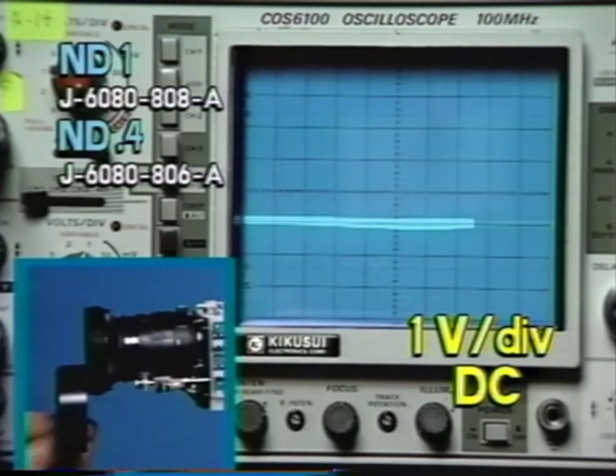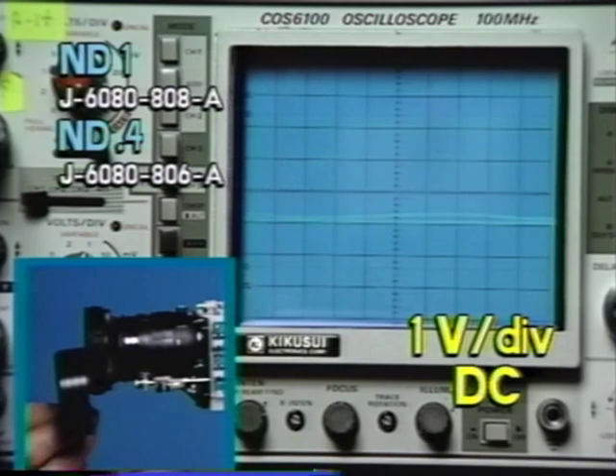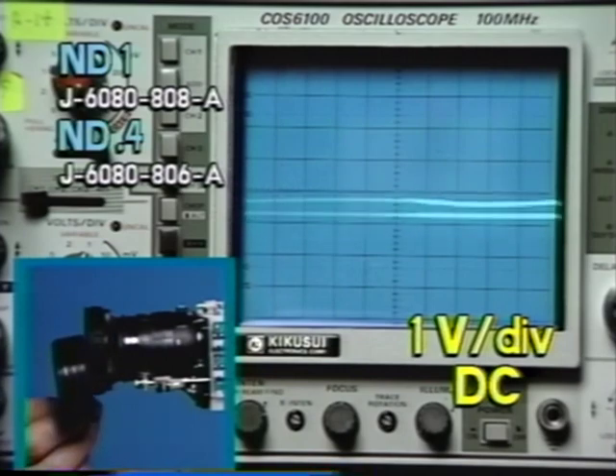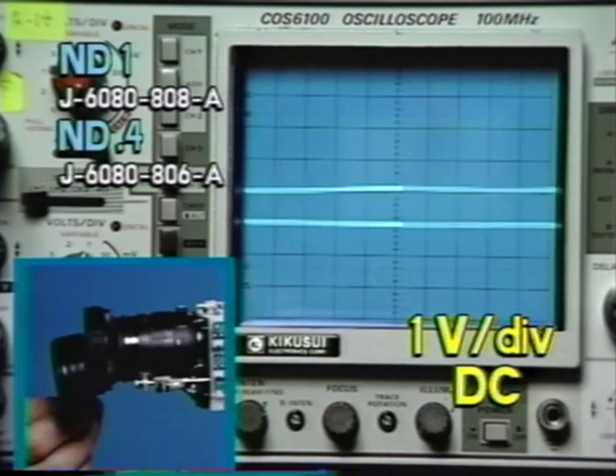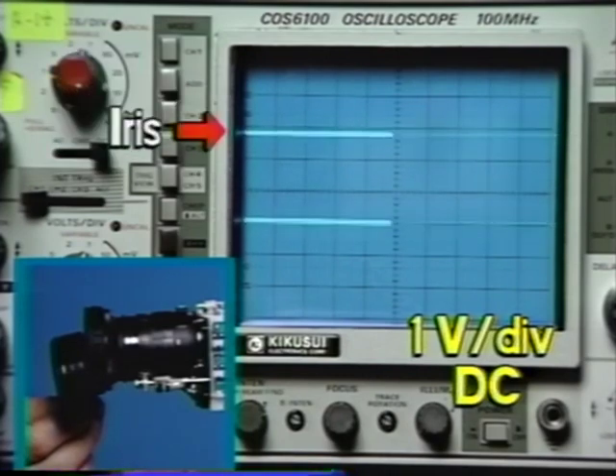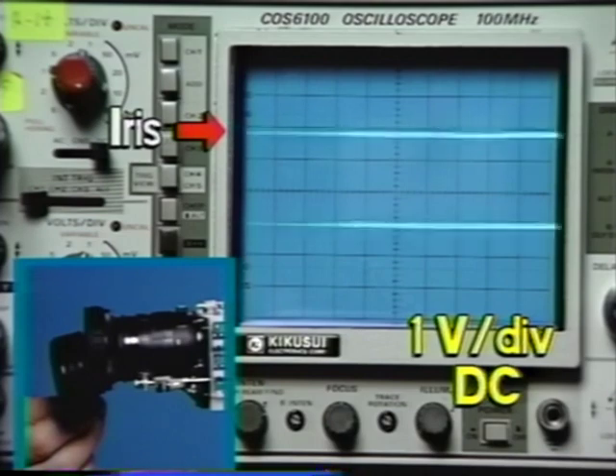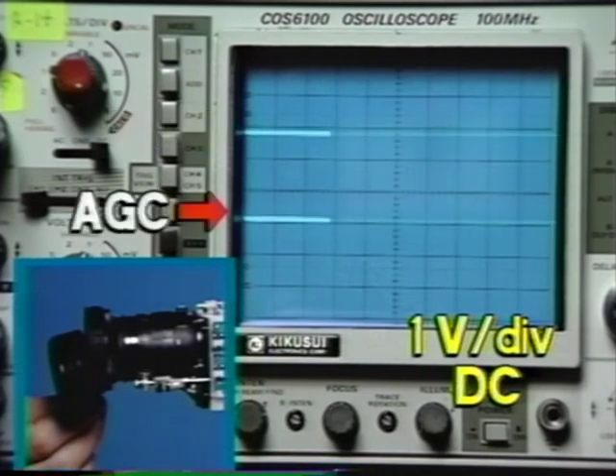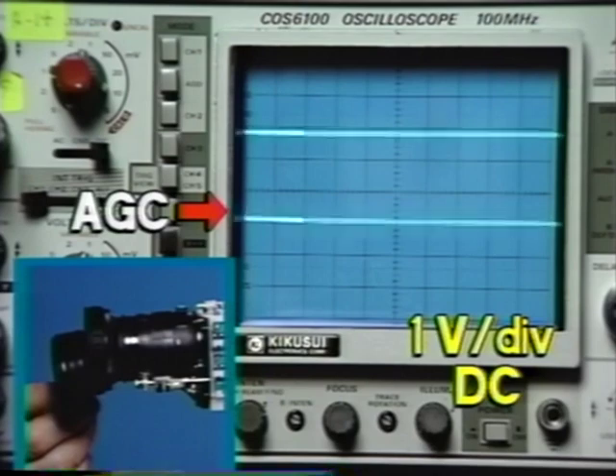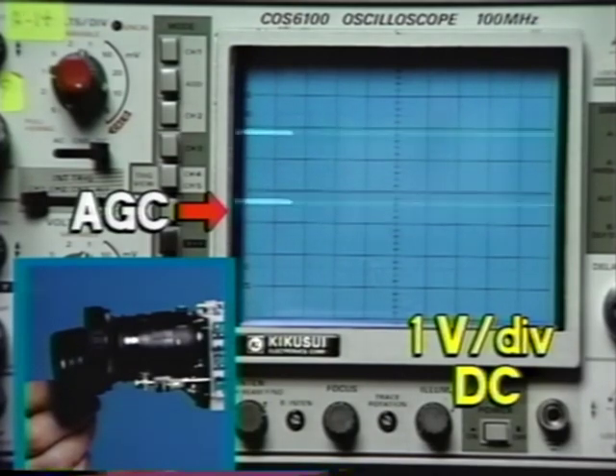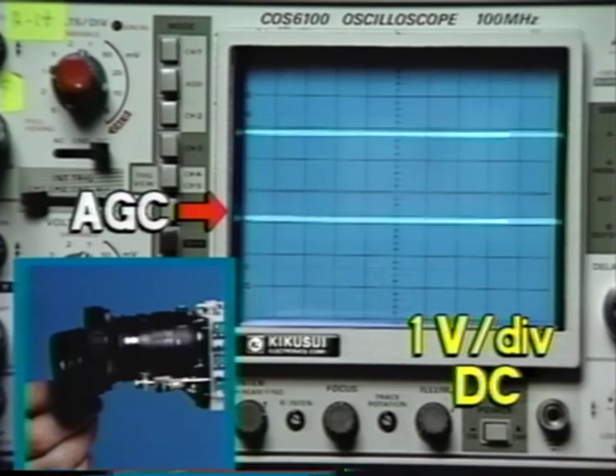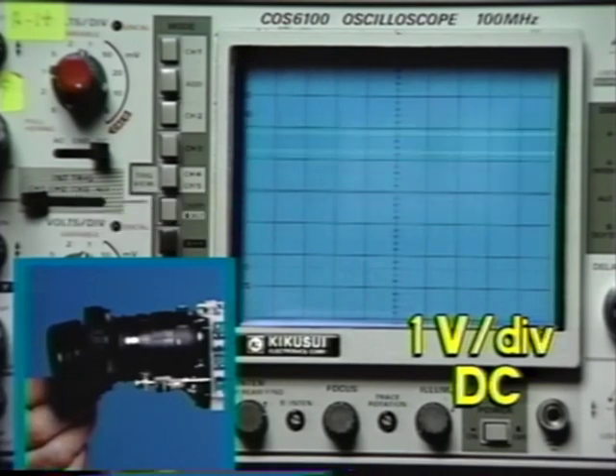Slowly place an ND1 and ND.4 filter combination over the lens. As the ND filters cover more and more of the lens, the iris voltage should increase to compensate for the reduced light level and to open the iris. When the iris voltage reaches the maximum 4 volts DC, it means that the iris is fully open. This threshold voltage level causes the AGC to increase to provide brightness gain control. This proves that the iris and AGC stages are both working to maintain brightness with reduced light input.